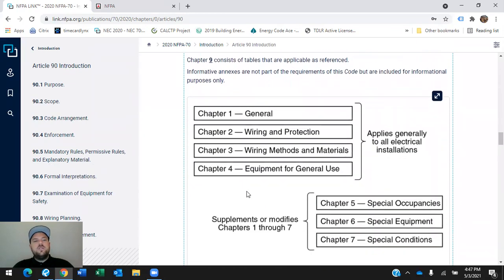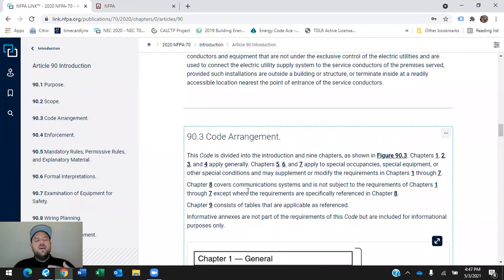90.3, this is important—this is our code arrangement. It gives us a visual understanding of how this code is broken out. This code is divided into the introduction and 9 chapters, as shown in figure 90.3. Chapters 1, 2, 3, and 4 apply generally—remember we heard that term in NFPA 70E as well—to all installations. Chapters 5, 6, and 7 apply to special occupancies, special equipment, or other special conditions, and may supplement or modify the requirements in chapters 1 through 7.